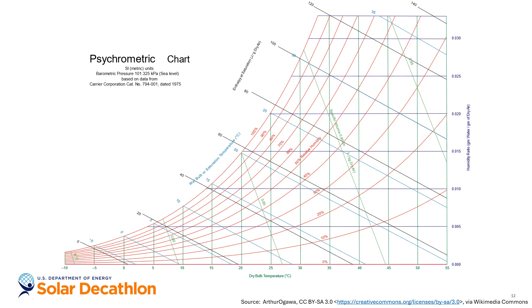So we've introduced key terms: dry bulb and wet bulb temperature, saturation temperature or dew point, relative humidity, and absolute humidity ratio. There are a few others to point out. First is enthalpy, shown as black diagonal lines and expressed as joules per gram of dry air. This is a measure of the energy content in the air taking into account both temperature and humidity. Enthalpy is useful when designing heating and cooling systems, but it's a complex topic beyond the scope of this course.